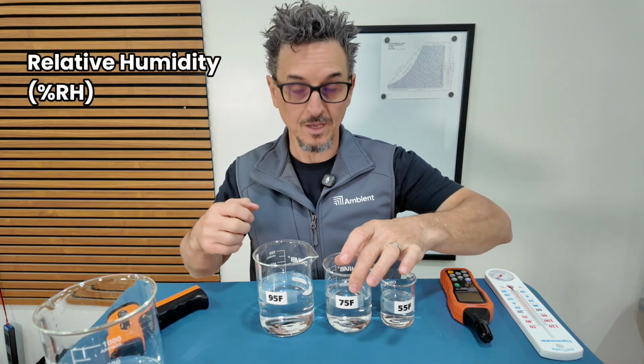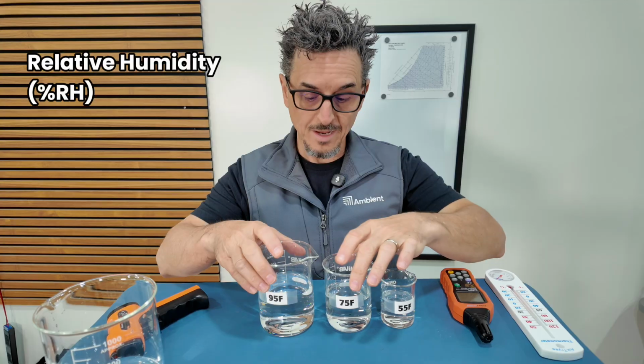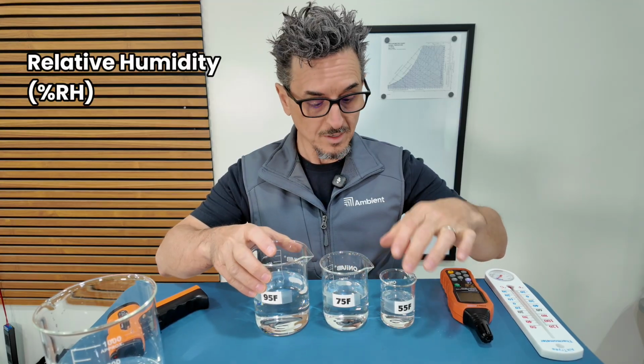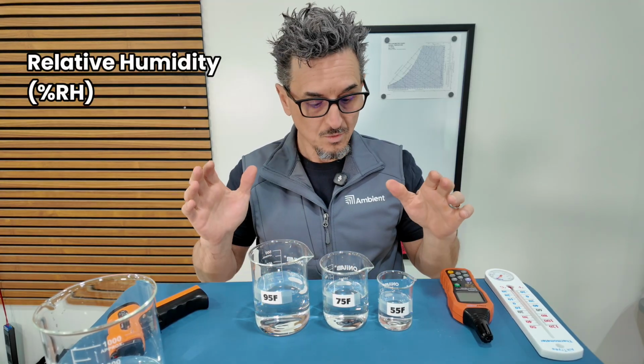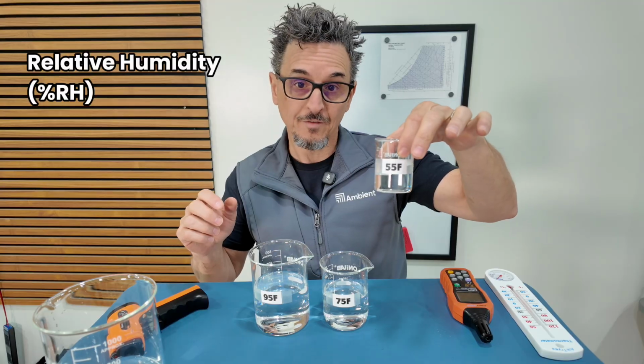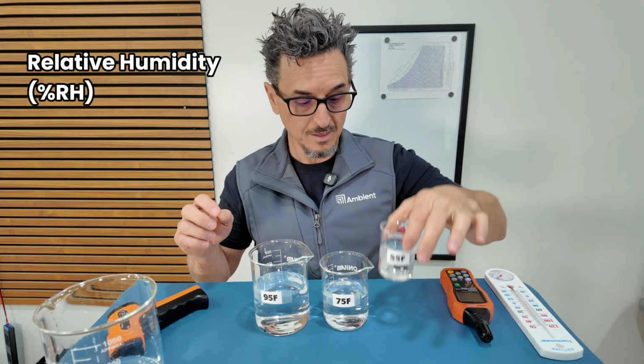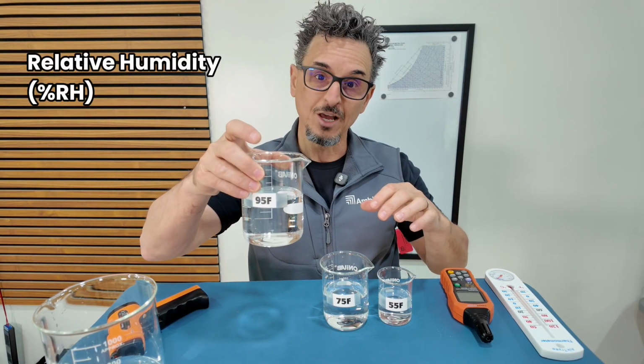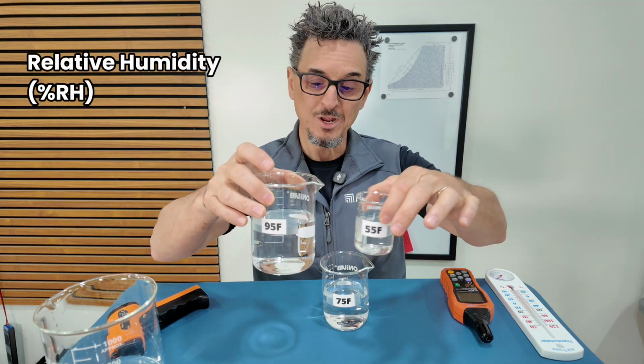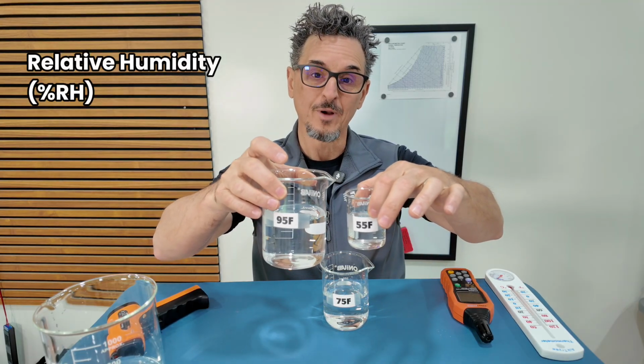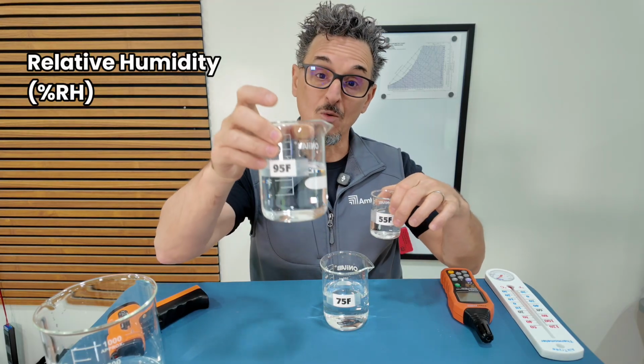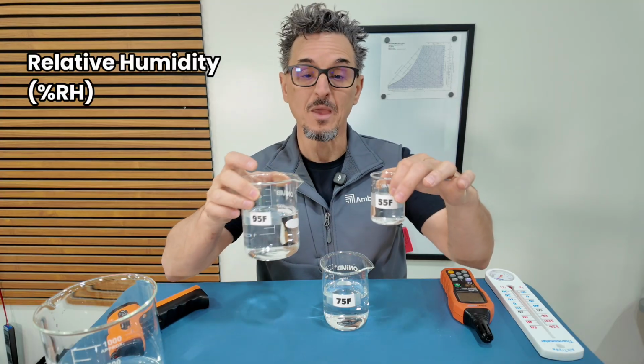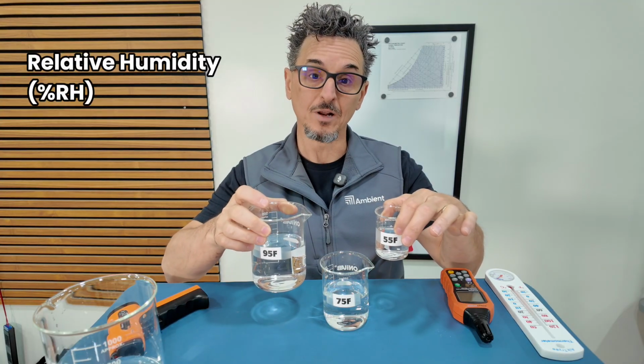Now here's the important thing to note. Here's the real important thing to understand about relative humidity. What do you notice about this 50% relative humidity state versus this 50% relative humidity state? What do you notice about the amount of moisture or the amount of water? Well, there's a lot more water here than there is here, but they both have 50% relative humidity.